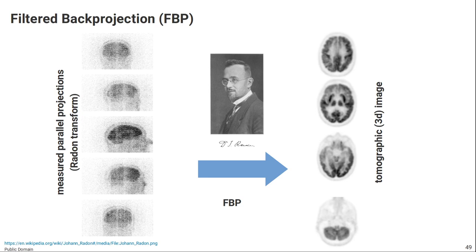The third reason is that for filtered back projection you need complete sampling. If you think of a PET scanner, you would need a perfect ring with many small crystals. But real PET scanners nowadays are usually not a ring, but rather a polygon made out of flat detector panels, and between those panels there are usually small gaps. That means in all of the views you have missing projection lines, and handling those in filtered back projection is complicated — if you don't, you get very interesting artifacts.